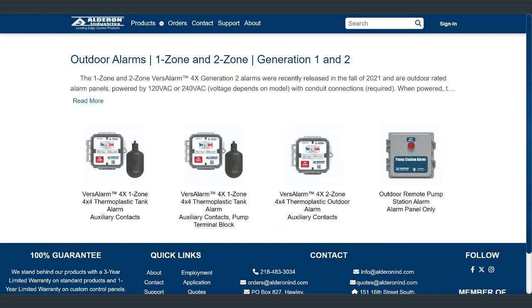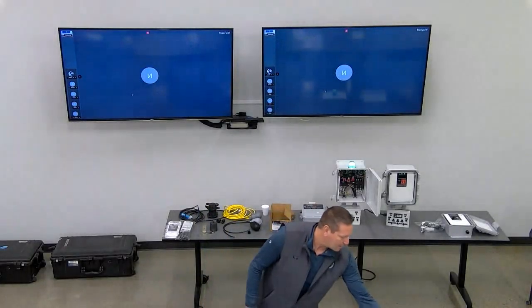And then alarm condition, if it's a 2 zone, you have zone 1 and zone 2 on each side. Or if you have both zones going off, they'll both flash. And this one has 9-volt battery backup terminals here. So you just stick a 9-volt battery in. If you lose your auxiliary or your 120 volt or 230 volt power, then your battery will keep your alarm active outdoors. And then you can get it with optional terminal blocks here. So if you wanted to bring separate incoming power for a single phase simplex pump, and then a pump float, and then your pump connection there too, you could get that as well. Pass that around. Has a lockable latch.